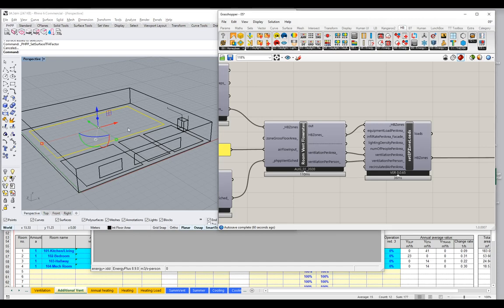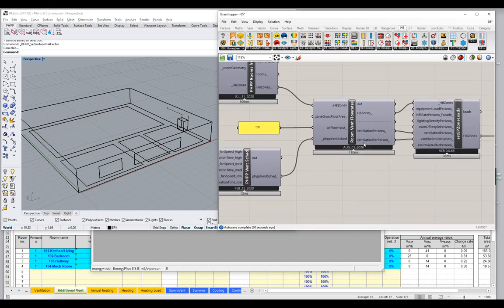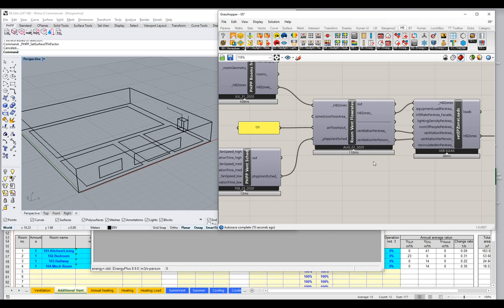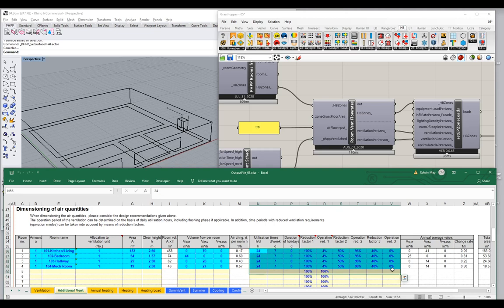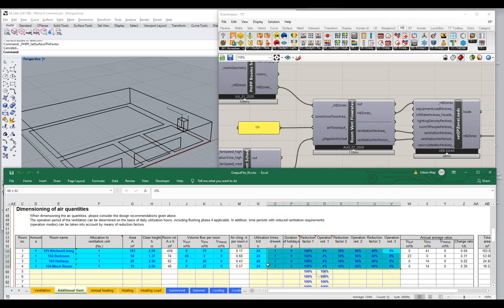Now one other element that we need to keep in mind here is that we also need to reset the schedules that Energy Plus is using. So not only do we have to reset the loads, but we do have to reset the schedules as well. And the reason we have to do that is because the way that the PHPP is going to calculate its energy consumption is that it's going to take all of this information and combine it together into a constant flow rate. So it's going to do it seasonally, once for the winter, once for the summertime.